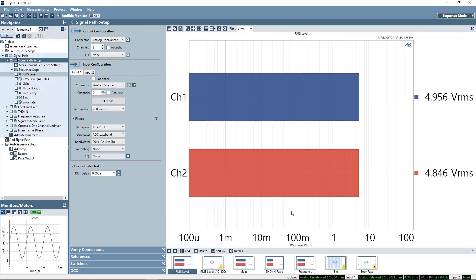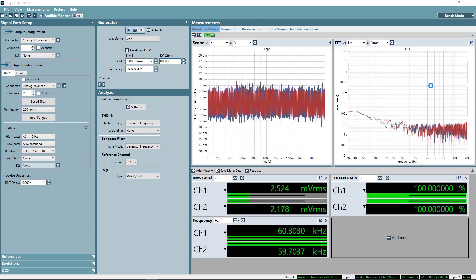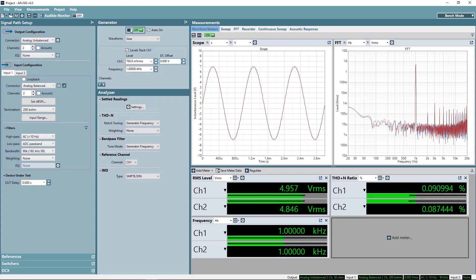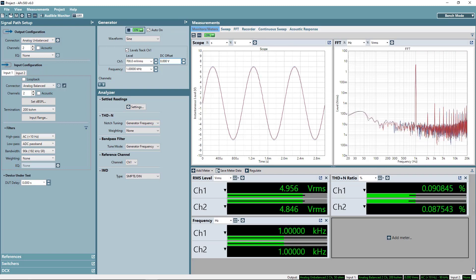This is the mode selection toggle switch. Sequence mode is the original mode of operation. It has a built-in test sequencer and reporting engine, well suited for validation, production tests, or any time a measurement or group of measurements must be repeated. Bench mode was added to APX500 in the version 4 software release. Bench mode is more of a free-form paradigm favored for research and development, providing more user control but no sequencing features and fewer measurement types.